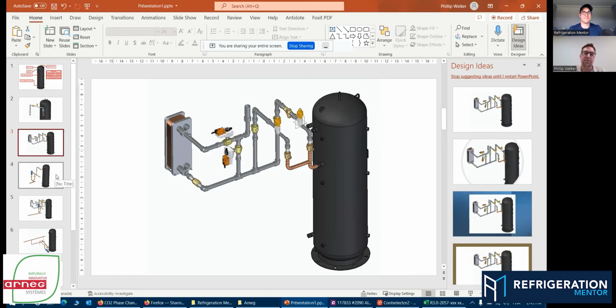But every time you close a valve, what did you just do? You just completely shock the system. You stop flow in the system. This is your primary valve. Here's your gas cooler, your primary valve that's providing, at this moment, that very cool liquid, because we're in subcritical, coming inside the flash tank. If we start closing valves, we're starting to diminish that effect, right?